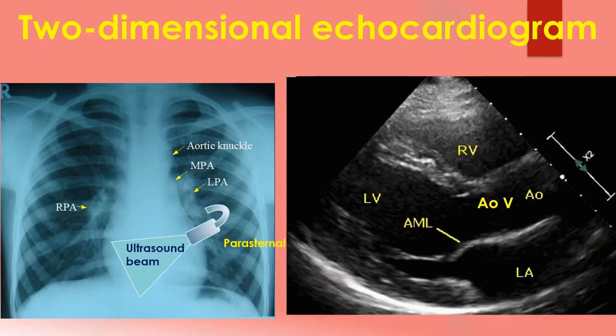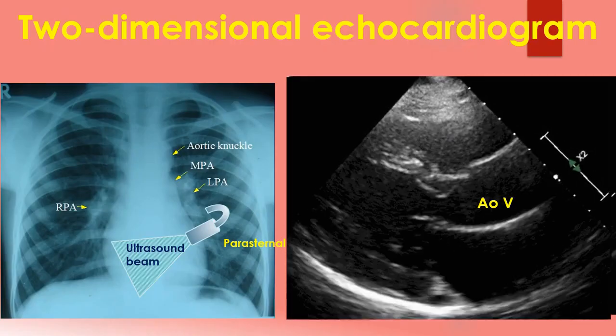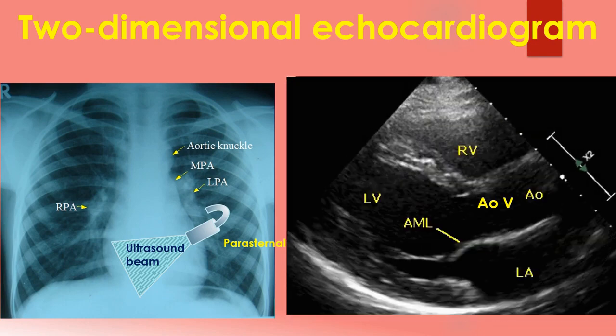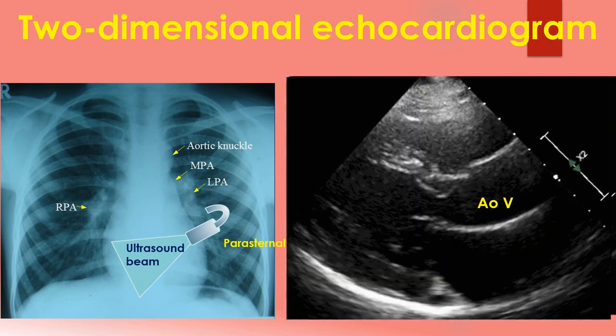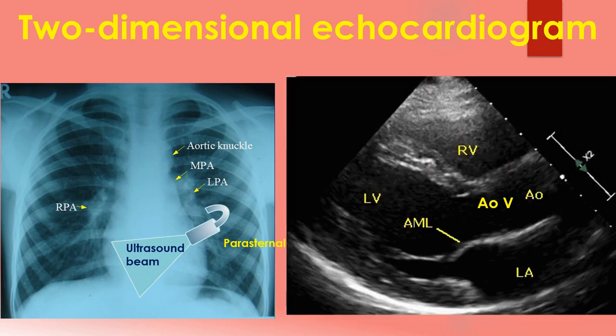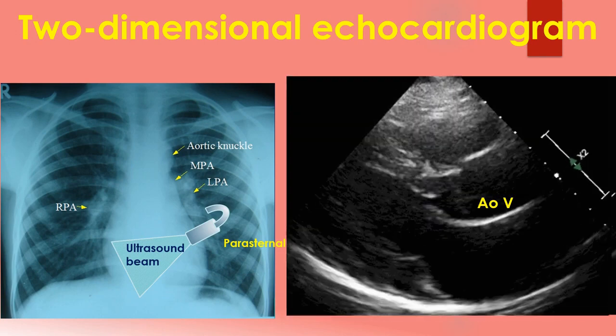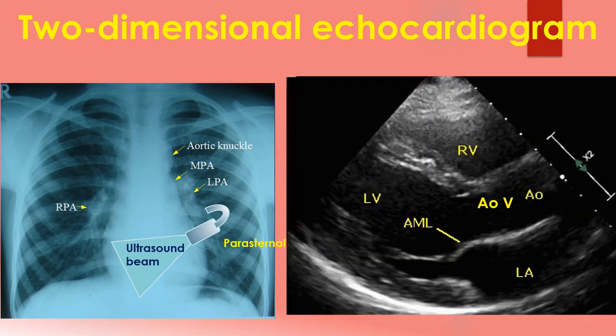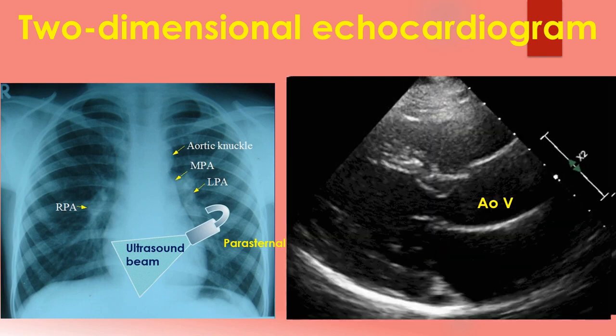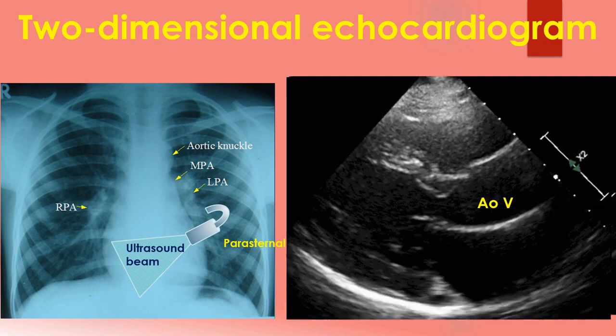During echocardiography, a transducer transmits the ultrasound beam towards the heart. Echoes received by the transducer from various structures of the heart are analysed by the echocardiograph and a graphical representation displayed on the monitor. The location of the transducer is at the top of the image sector. Structures nearer to the transducer are shown at the top of the image and those away from the transducer at the bottom.